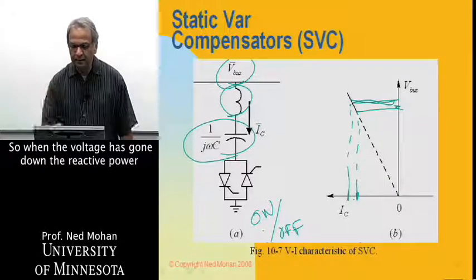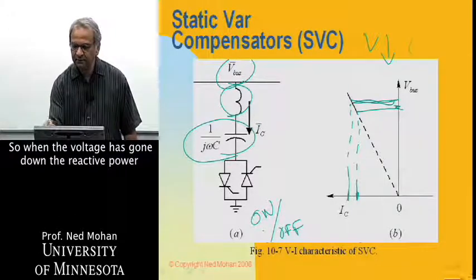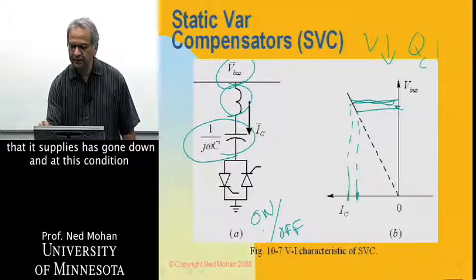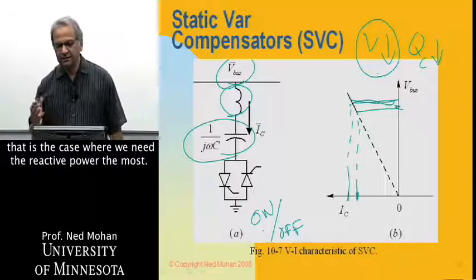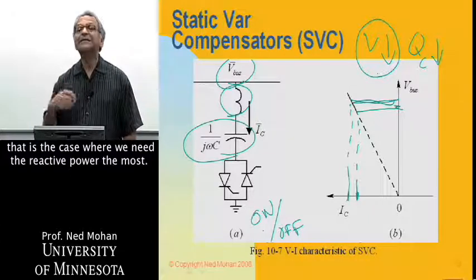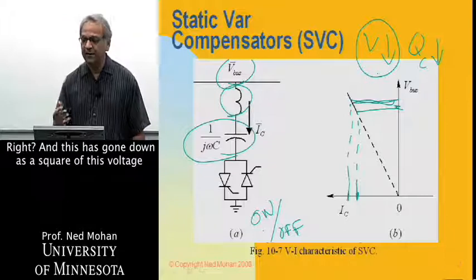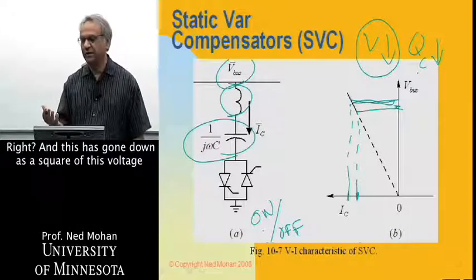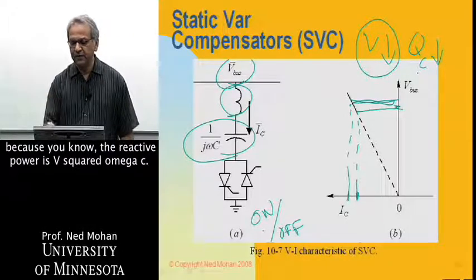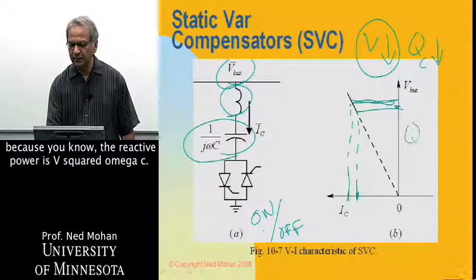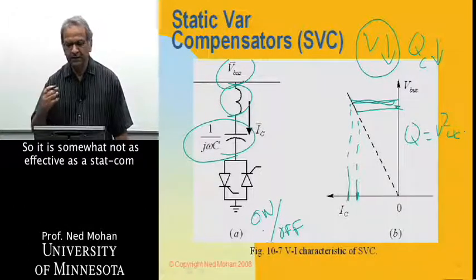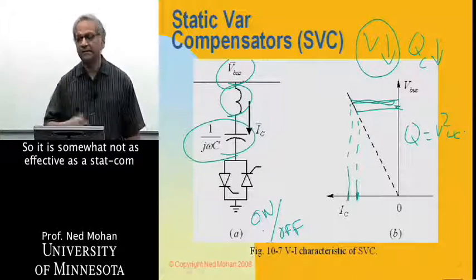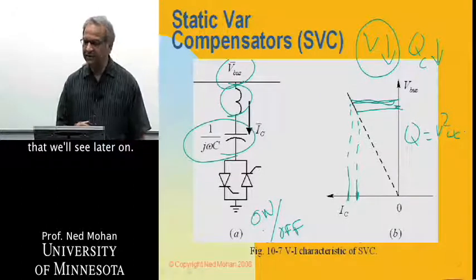When the voltage has gone down, the reactive power supplied has also gone down — and that is precisely the condition where we need reactive power the most. The reactive power goes down as the square of the voltage, since reactive power equals V² × ω × C. So this is somewhat less effective compared to a STATCOM that we will see later.